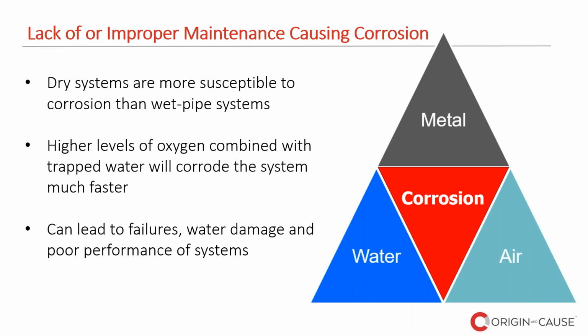When it comes to corrosion, corrosion happens in both wet and dry systems. However, dry systems are more susceptible because they have a chamber full of air and some residual water, and those are the preferred conditions for corrosion to happen. So you have a lot of oxygen, some water, corrosion happens. If you see a full pipe, then over time that level of oxygen is going to reduce, and therefore corrosion is going to reduce as well.